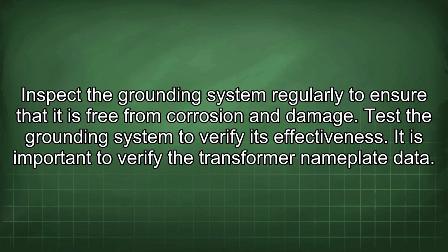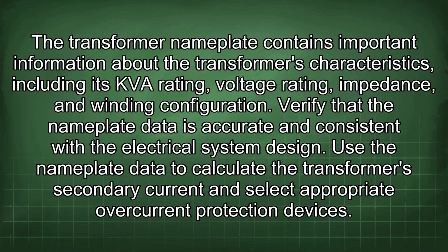It is important to verify the transformer nameplate data. The transformer nameplate contains important information about the transformer's characteristics, including its kVA rating, voltage rating, impedance, and winding configuration. Verify that the nameplate data is accurate and consistent with the electrical system design. Use the nameplate data to calculate the transformer's secondary current and select appropriate overcurrent protection devices.